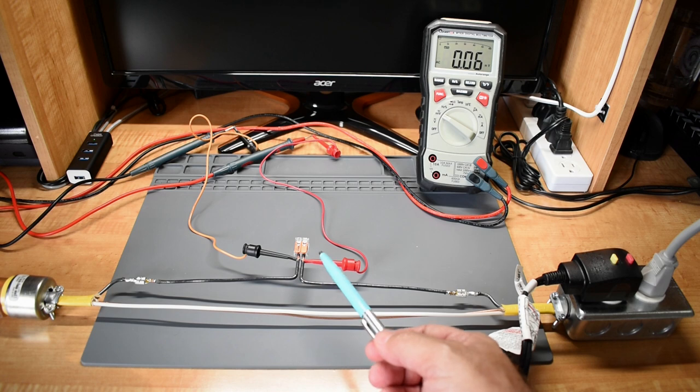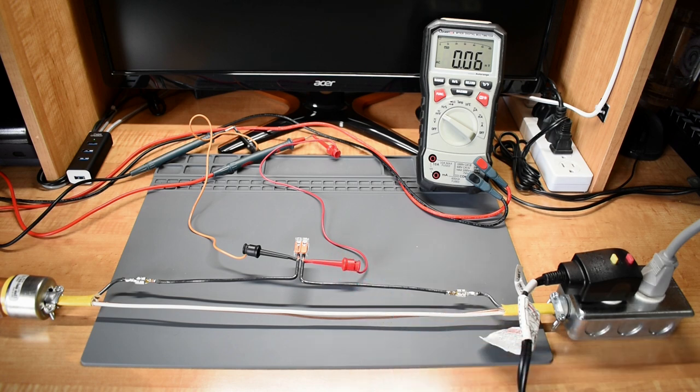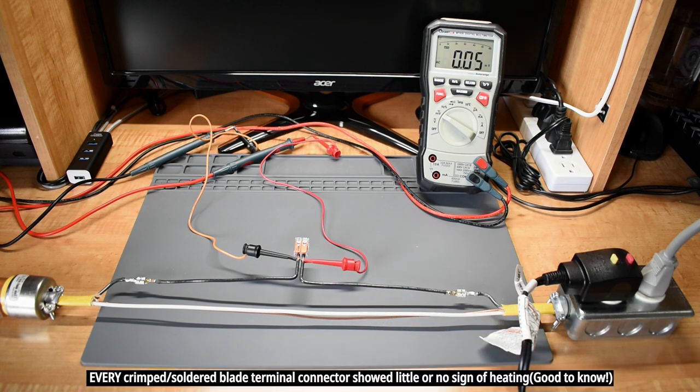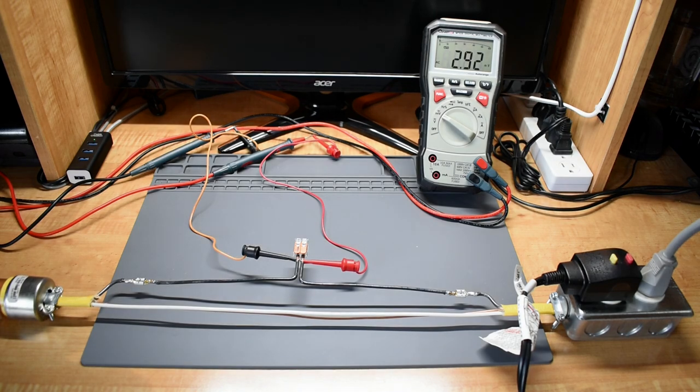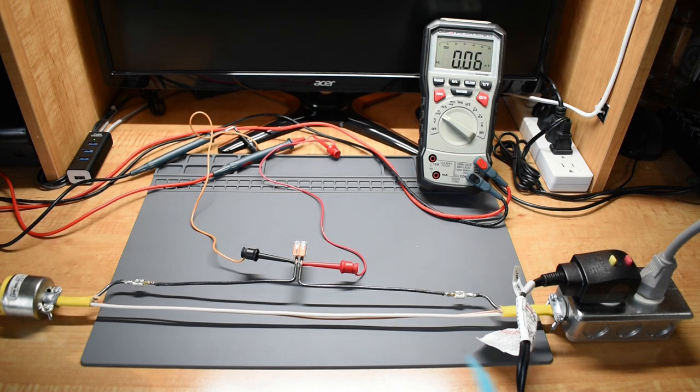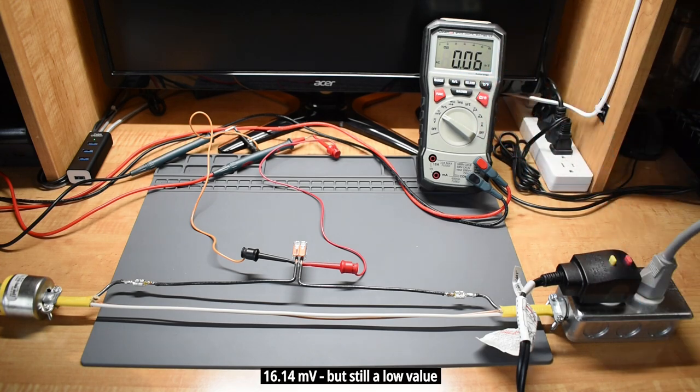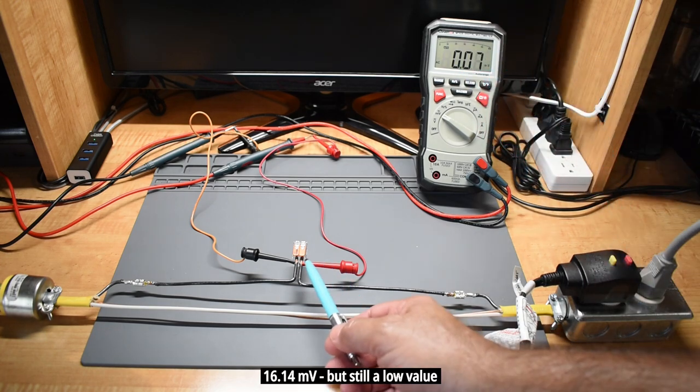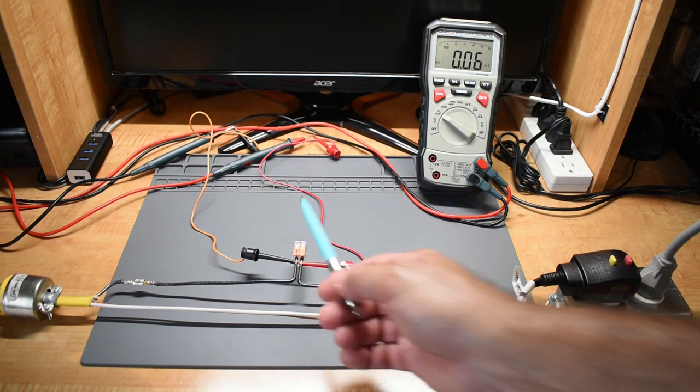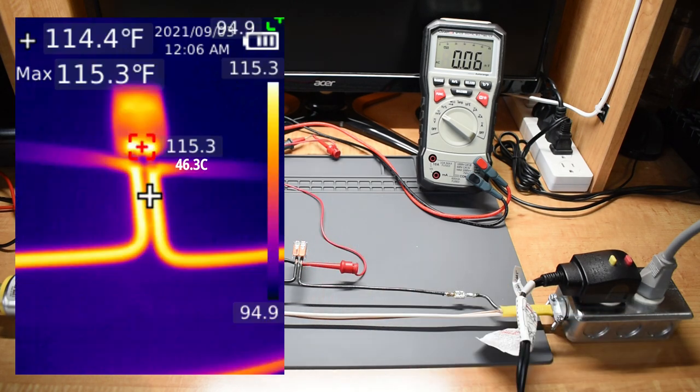The last connector is the one that wiggled the most, the Wago 221. As you just saw, the Wago 221 had the highest voltage drop out of all of them, and I expected that because the wires wiggled the most within the connector. Right here you can see a temperature reading of this connector at the end of the test.